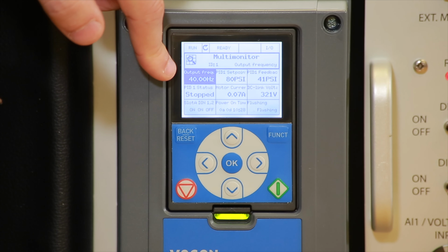Next is the motor nominal speed. Whatever the RPM on your motor nameplate is, enter it here. The ampacity of the motor. If it's a submersible pump motor, the service factor amps should be entered here instead of the full load amps, only if you know that the actual pump motor will go into service factor. So this is very important if you're running a submersible pump application with this drive. In our case, we're going to put the motor FLA of this particular motor. It's 1.9.